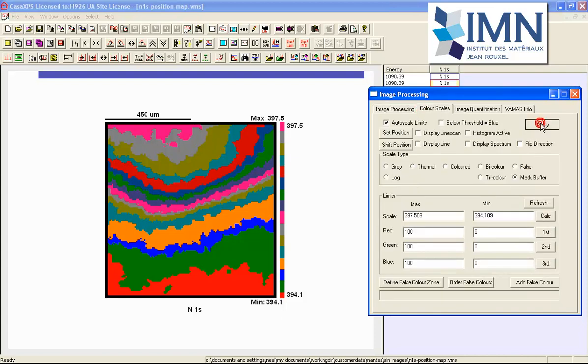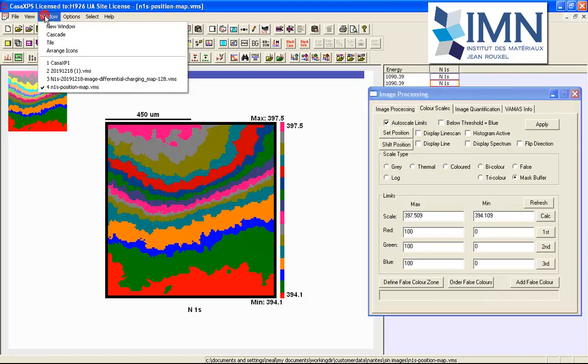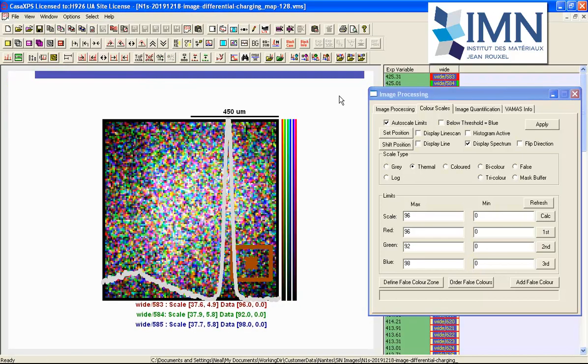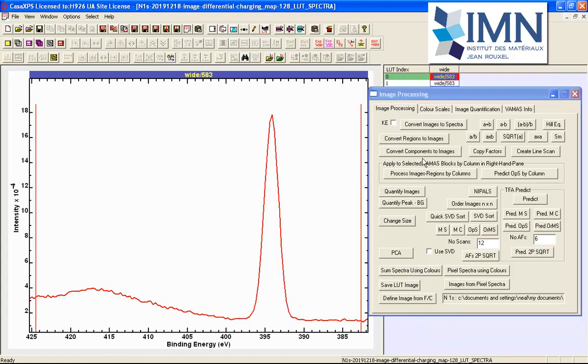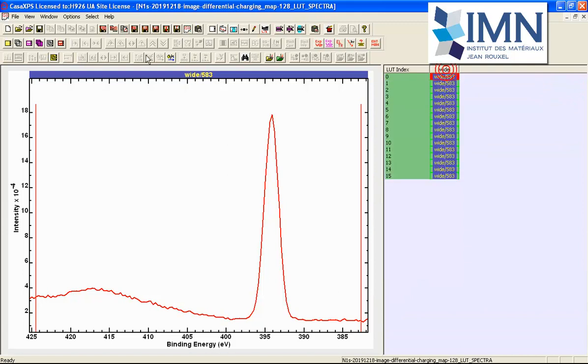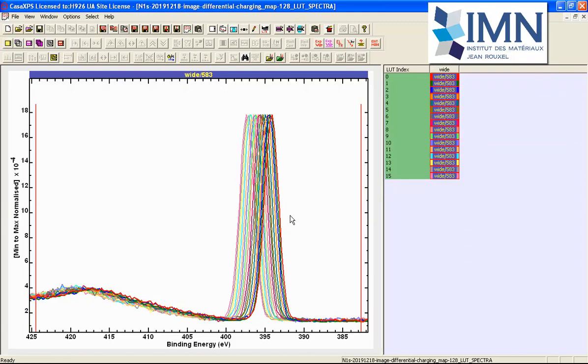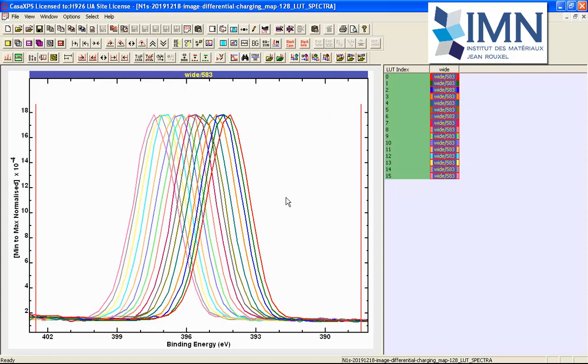What I'm going to do now is define this as my false color image. Just verify that I have a mask that corresponds to this. This is the mask that is currently active. I can apply this to these images that are currently overlaid in the active tile indicating there is a nitrogen peak here. If I now use sum spectra using colors, rather than using a box of pixels and summing the spectra of these pixels to form this spectrum, the false colors will be summed to produce a set of different spectra. Rather than seeing a single spectrum, I now see a set of spectra and these all correspond to the different colors in that false color image. At this point we have spectra that look like individual peaks and they've all been shifted as a consequence of different charge states on the sample across that sample surface.